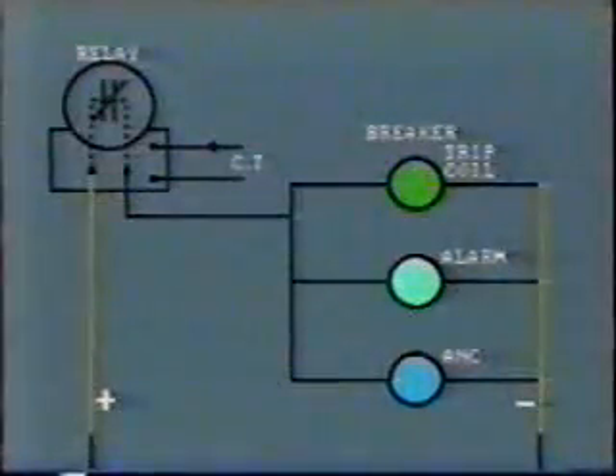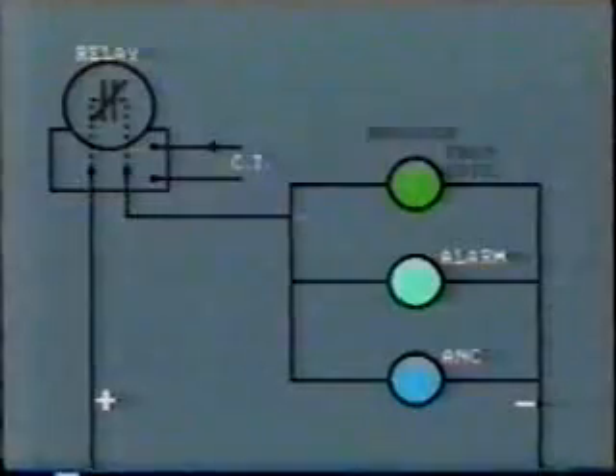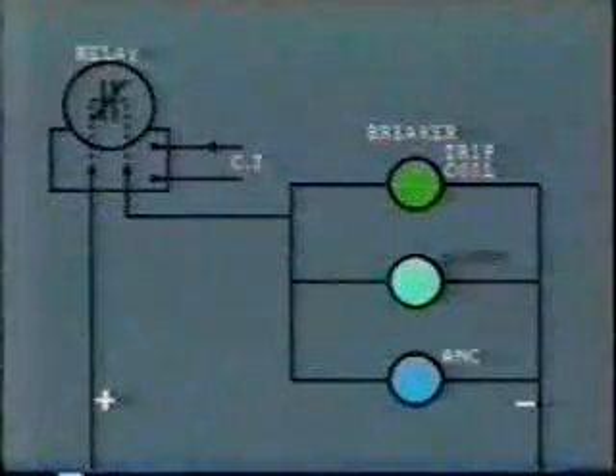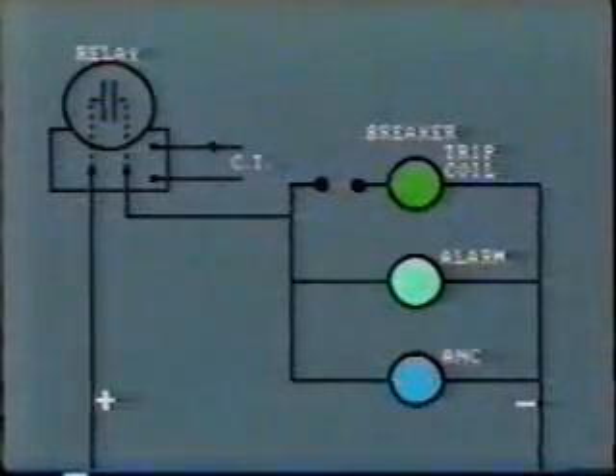In the simplest circuits, this relay output will apply DC to the tripping circuit and so cause the appropriate breaker to open and initiate the corresponding alarm and annunciator. If we are carrying out a series of tests, we do not want the circuit breaker to repeatedly open and close. In this case, it is usual to isolate the particular trip circuit using isolation links or blocking switches, and provide other means of indication, perhaps a lamp or voltmeter.